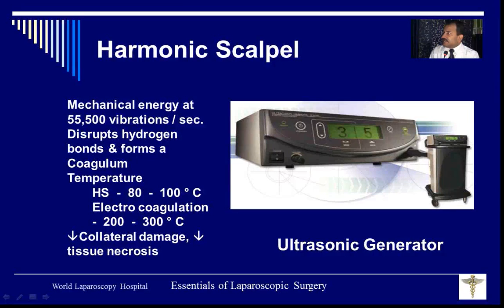In the machine, if you will see here, there is a setting. This minimum setting can go from 1 to 5. If you keep it at 1, that means vibration is 15,000 per second. 2 means 25,000, 3 means 35,000, 4 is 45,000 and 5 is 55,000. So if you have to coagulate more and cutting you need slow, you will keep it at 1. And if you have to cut faster and you want less coagulation, you will keep it at 5. You will use minimum and maximum.